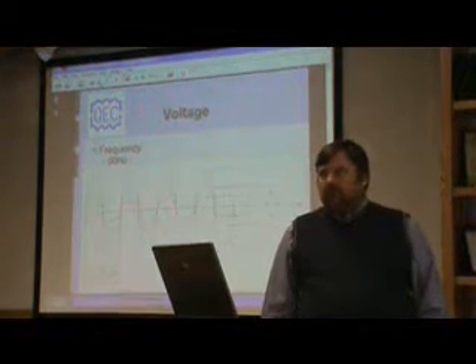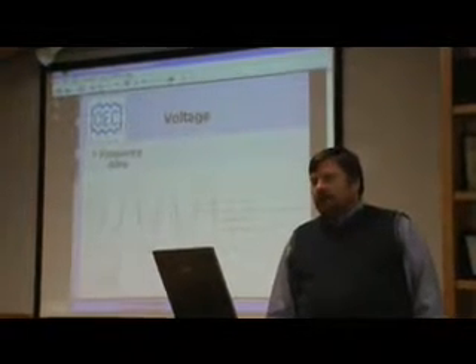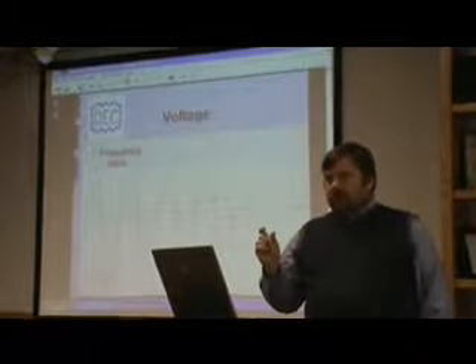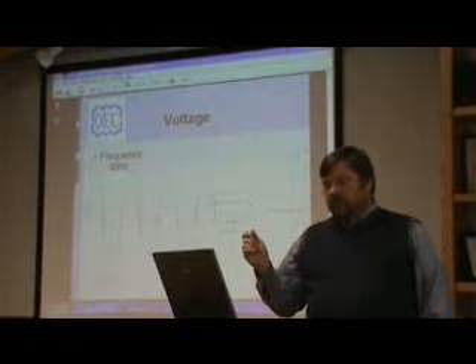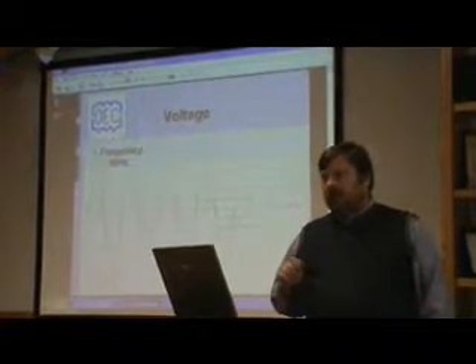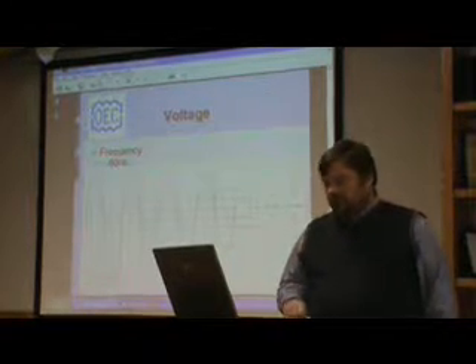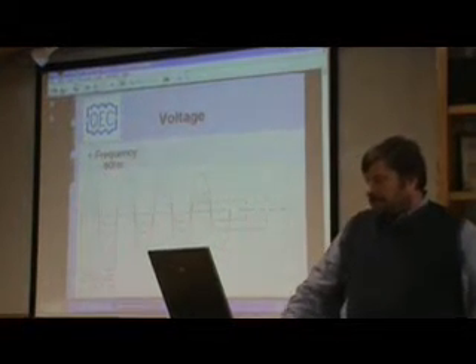system. And a lot of your three-phase panels will have a phase monitor to make sure that you have all three phases and they're working within the realm. A lot of the phase monitors are frequency sensitive. So if your generator is not really pulling at the full 60 cycles, and you can adjust that by the speed of the generator, you're going to have some phase problems with your phase monitors.